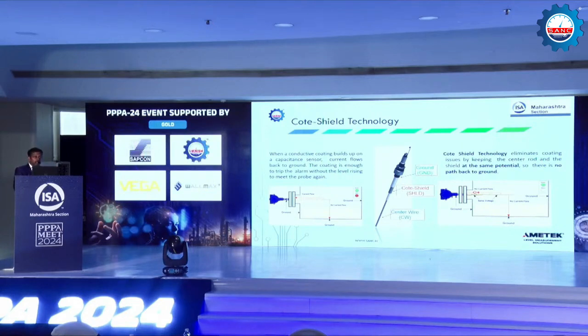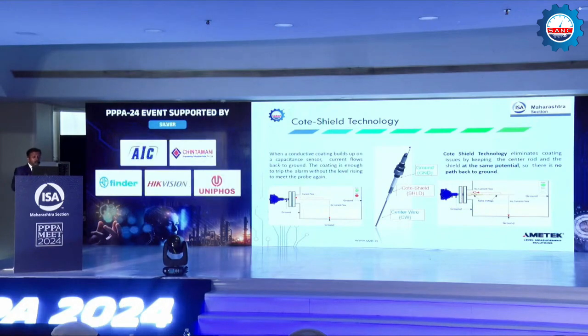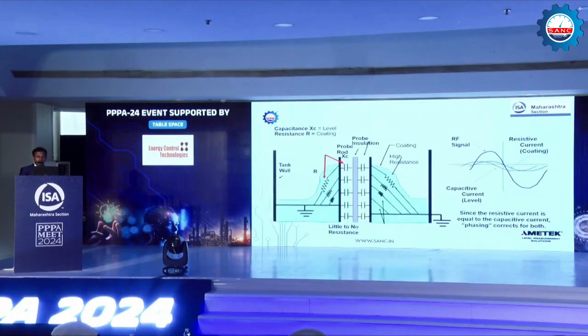Of course, during installation, we suggest a few considerations, like the nozzle should be at a 45-degree angle, which would be better. And the Cote-Shield length should extend beyond the nozzle length, so we get a better installation and better coating rejection. This is how Cote-Shield technology is implemented in level switches. And in transmitters, it is implemented in a slightly different way.